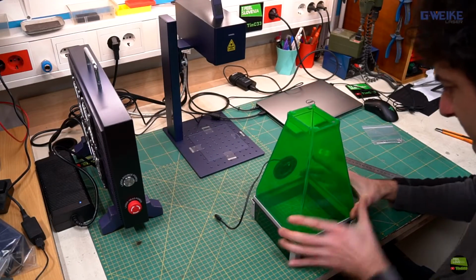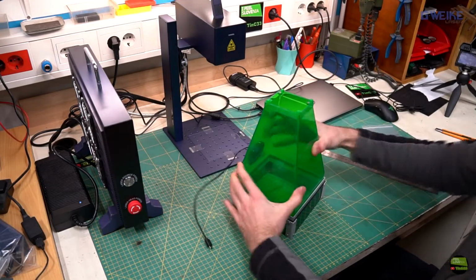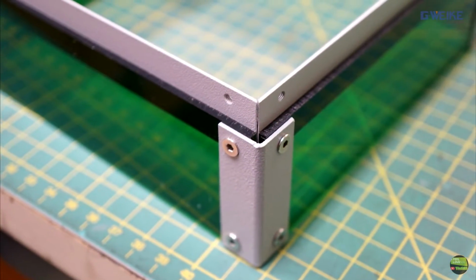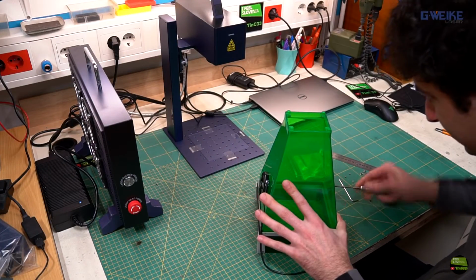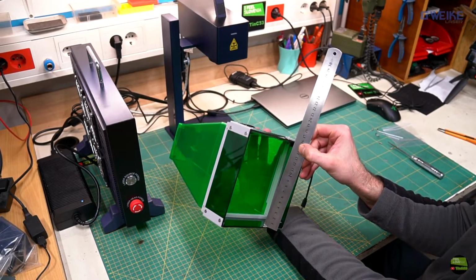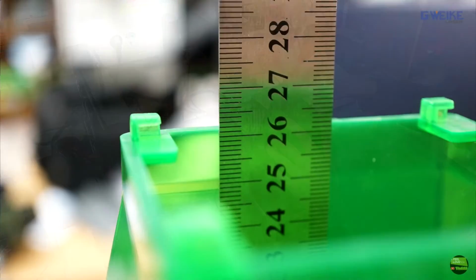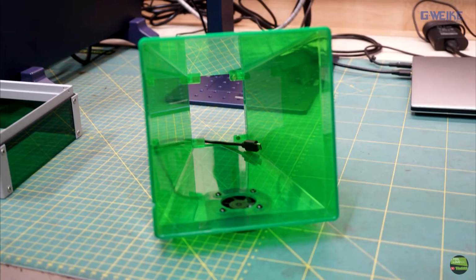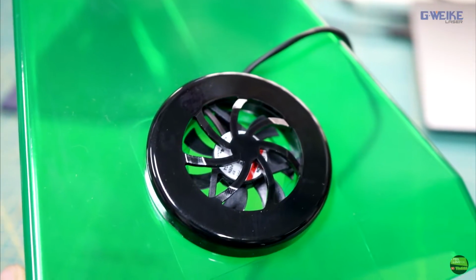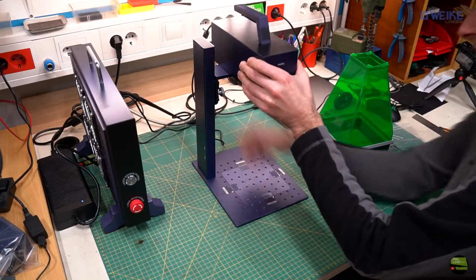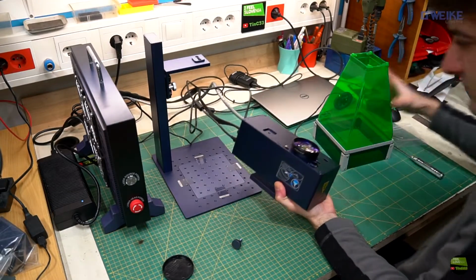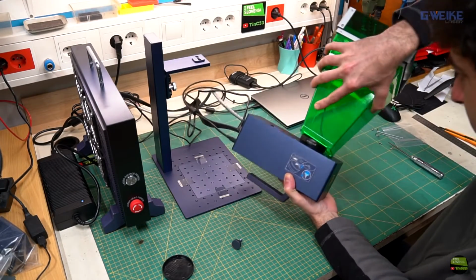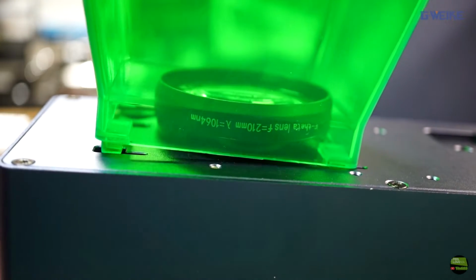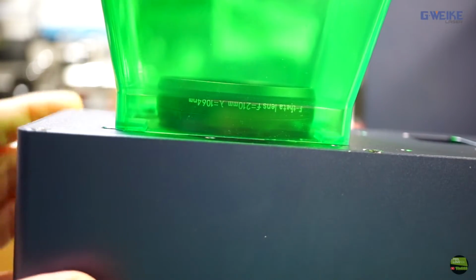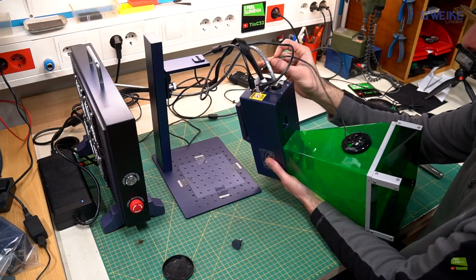To assemble, simply slide the shield into the extension and gently tighten a few screws around. After assembly, the protective shield is about 160mm wide at the bottom and exactly 261 height, which is the focal distance of the laser. On the back side of the shield is a small fan which provides clean air inside of the shield. To mount the shield, just take the laser off the stand, remove the lens protective cap, put on the shield and slide it into the grooves. When the shield is attached, just plug the micro USB cable on the back side of the galvo unit.